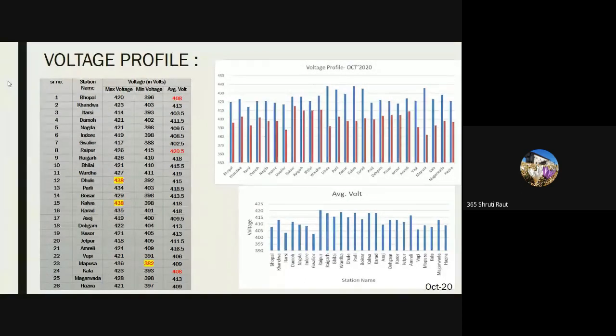So HV problems, high voltage problems, are related to the amount of reactive power present in a system. We know that when reactive power is high, the efficiency of the system decreases. So we need reactive power compensation for this system. In the Western region, we use static shunt compensation, where switched and non-switched reactors are used in this system. There are a number of reasons why high voltage occurs, that is due to loading of line, inadequate reactive compensation, and Ferranti effect in EHV and UHV.